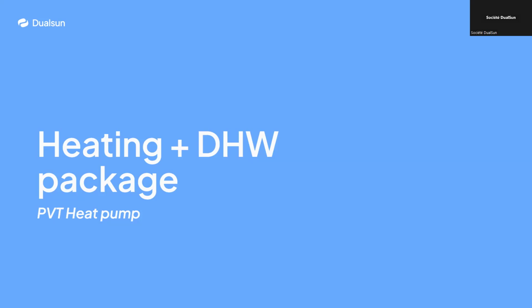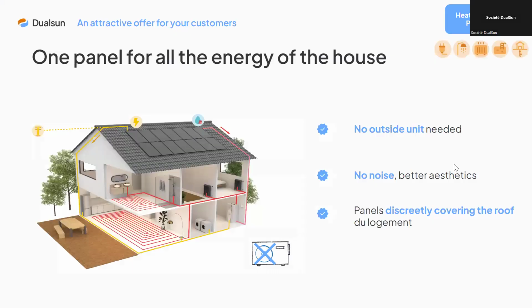The offer we're proposing is based on the same principle, with the difference that the cold source on the collection side will be the glycol water charged with calories as it passes through the panels. This is the heat pump, the PVT heat pump offer.